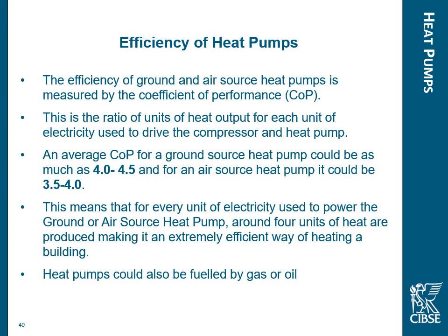So the efficiency of heat pumps, although I've talked about 300, 400, 500% efficient, is measured in something called coefficient of performance, COP. So a COP of 3 is in fact 300%.